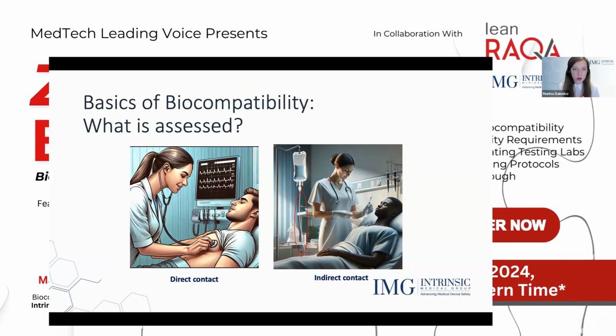Actually, as I started this conversation, if we have a device that is categorized as a medical device, and it's a registered medical device, we need to perform biological evaluation in any case, even if it doesn't have any contact with the patient. What does it mean? It means that we just need to prepare a document that states: okay, we have a medical device, it doesn't have any contact with the patient. We don't need to perform biological evaluation on it, but we need to document this information. So it's a requirement to assess it in any way.